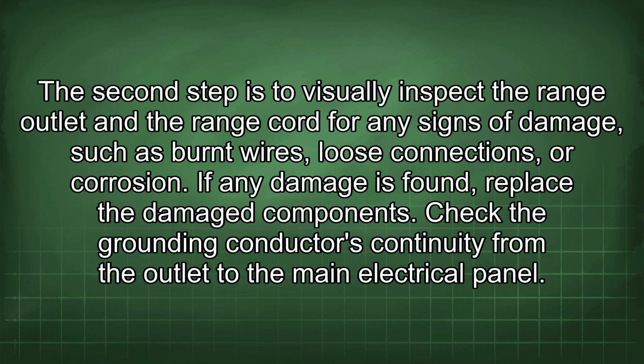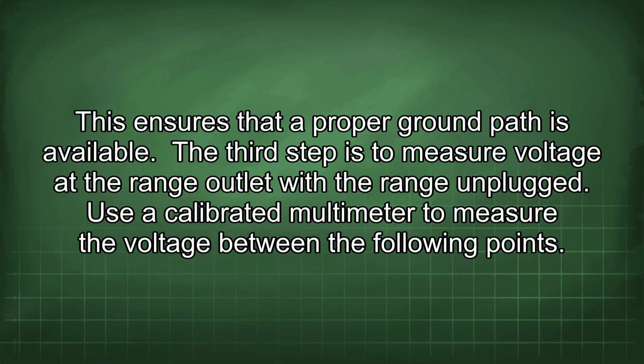The second step is to visually inspect the range outlet and the range cord for any signs of damage, such as burnt wires, loose connections, or corrosion. If any damage is found, replace the damaged components. Check the grounding conductor's continuity from the outlet to the main electrical panel. This ensures that a proper ground path is available.